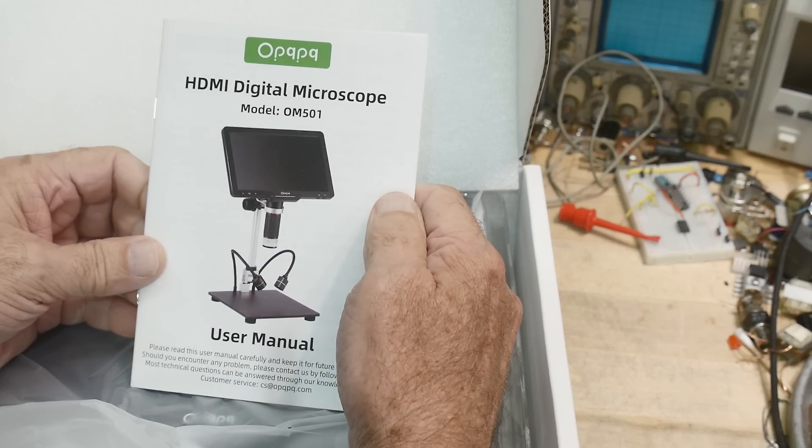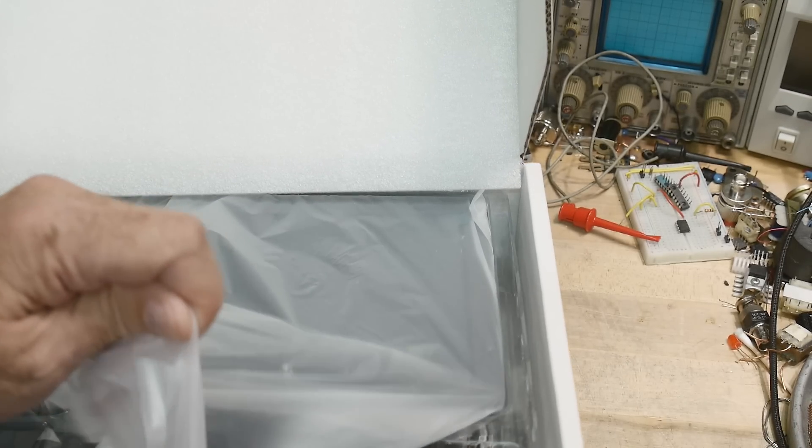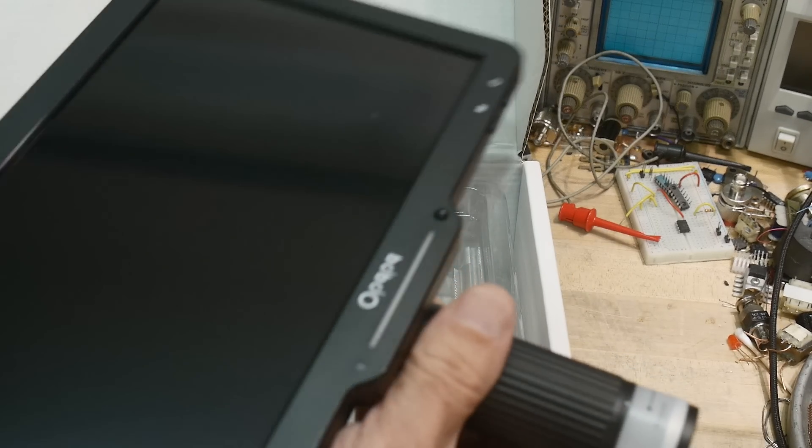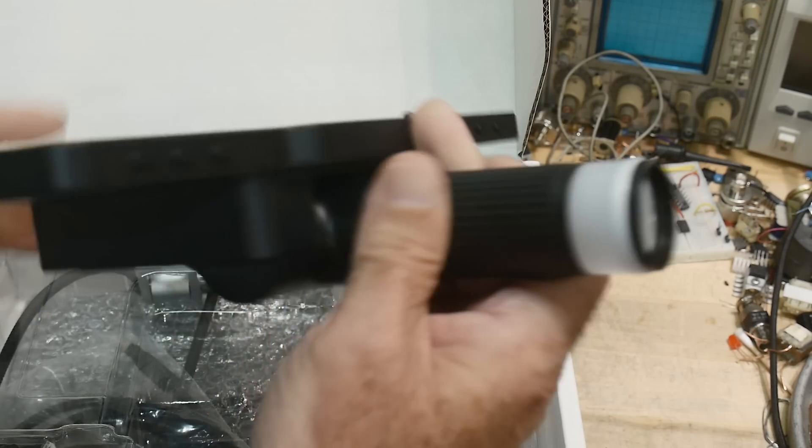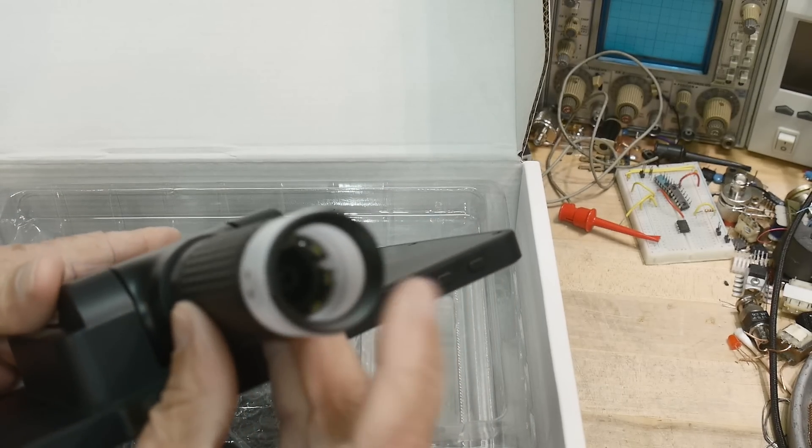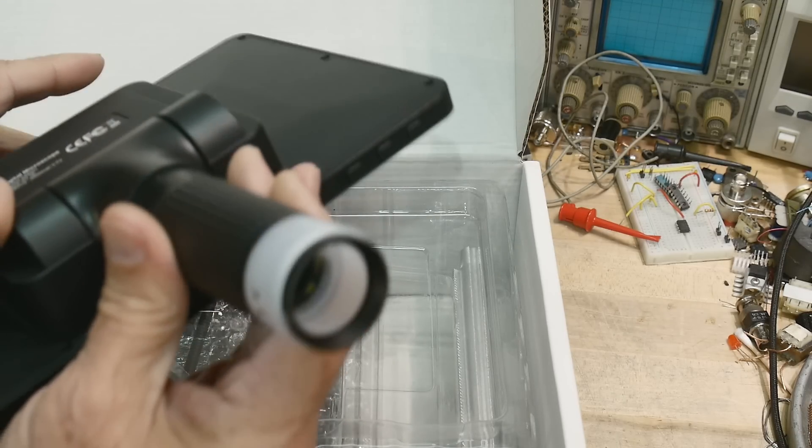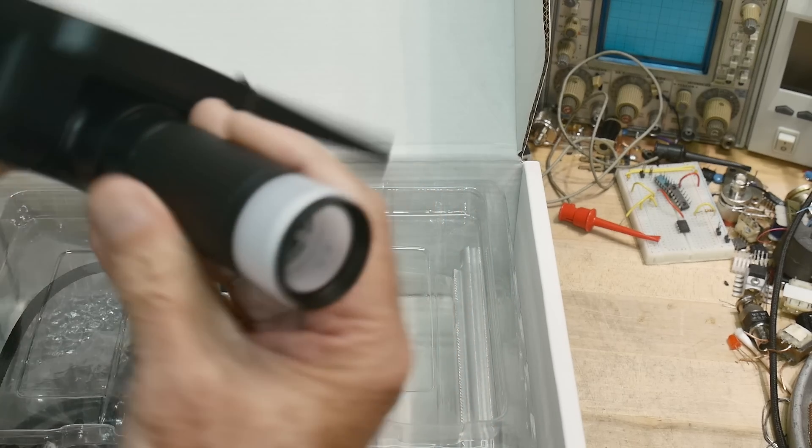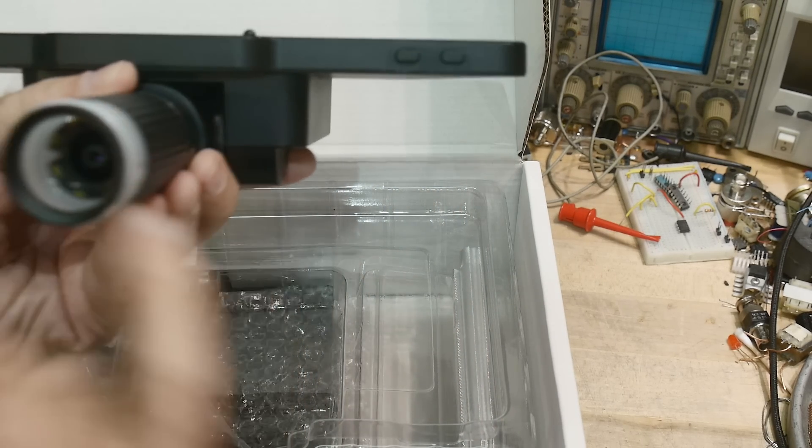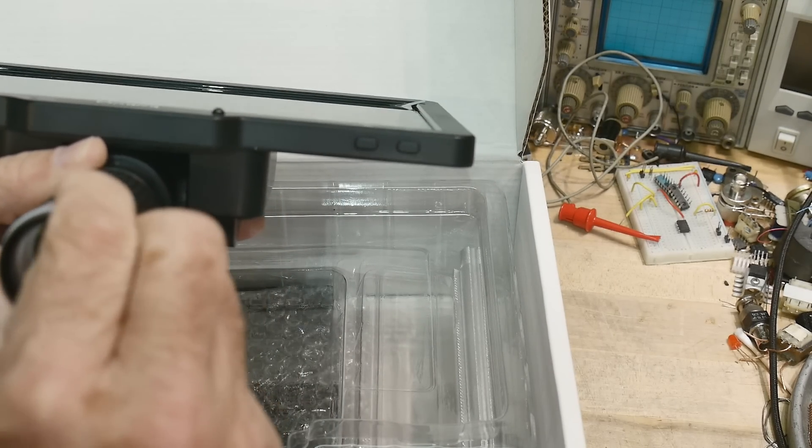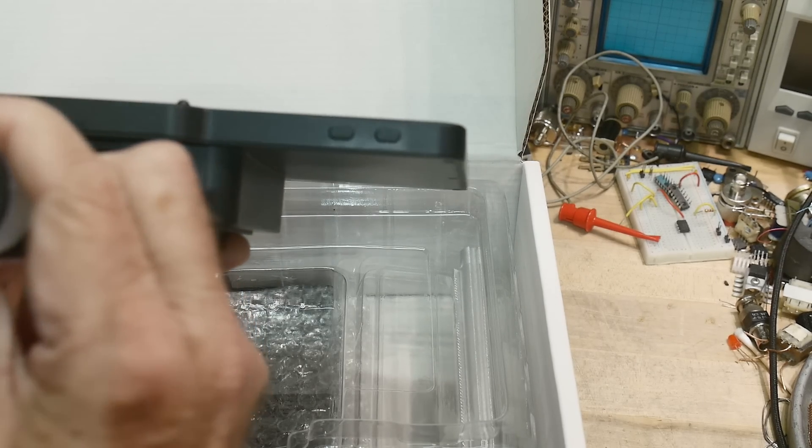Let's take a look at what we get inside here. This is the actual microscope. It doesn't look like a microscope - it's an LCD panel with a lens on it, like a camera except the lens is a zoom micro lens. The ocular is built in, and this one has a light source built in - a ring light source in the front. It's got a polarizer also, oh wow. Okay, this one's fancier. Let me put it together and we'll take a look at it.